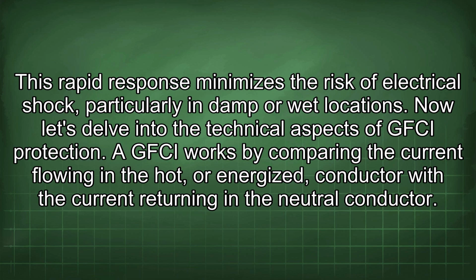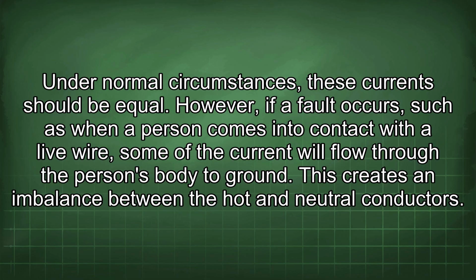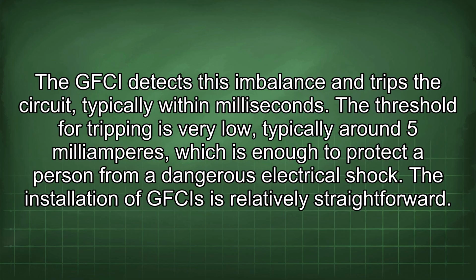Now let's delve into the technical aspects of GFCI protection. A GFCI works by comparing the current flowing in the hot or energized conductor with the current returning in the neutral conductor. Under normal circumstances, these currents should be equal. However, if a fault occurs, such as when a person comes into contact with a live wire, some of the current will flow through the person's body to ground. This creates an imbalance between the hot and neutral conductors. The GFCI detects this imbalance and trips the circuit, typically within milliseconds. The threshold for tripping is very low, typically around 5 milliamperes, which is enough to protect a person from a dangerous electrical shock.